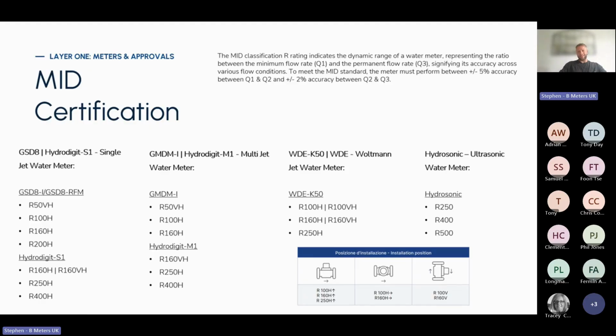Same on the Woltmann meters, and then it varies when you get to the ultrasonic water meters, because these are really able to have much better accuracy at lower flows. So in an ideal world, you would go ultrasonic for everything, because you're not going to have moving parts, you're not going to lose accuracy. The accuracies are going to be better over the lifespan of the meter. There is no jeopardy with installation positioning. For example, multi-jet meters you can't install typically with a dial facing down.